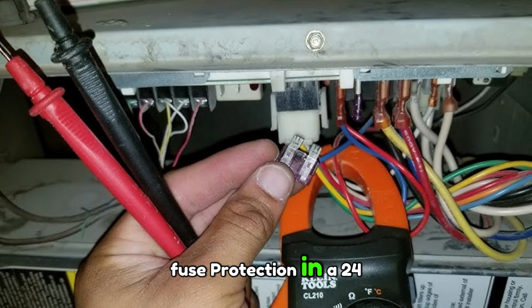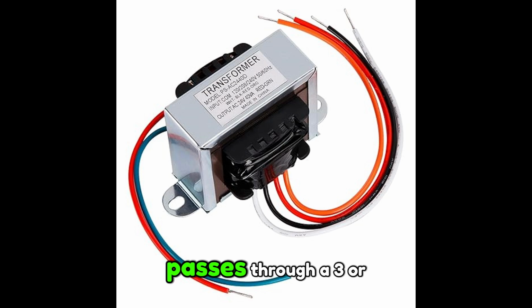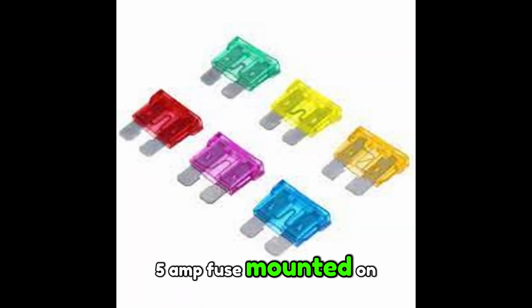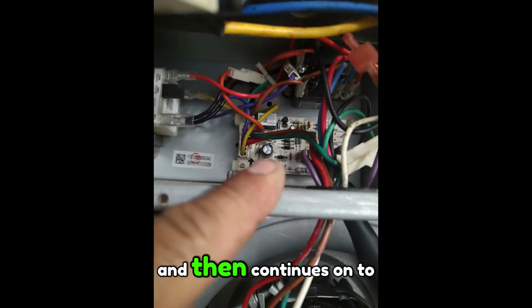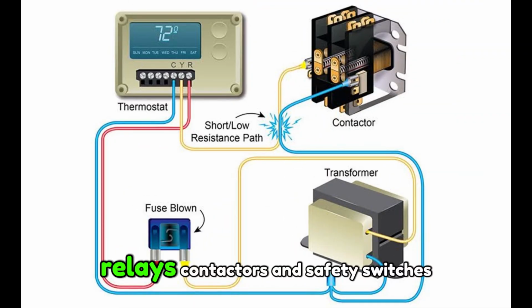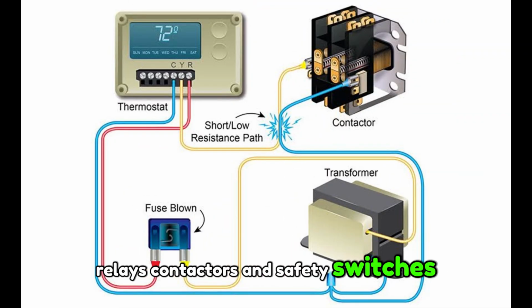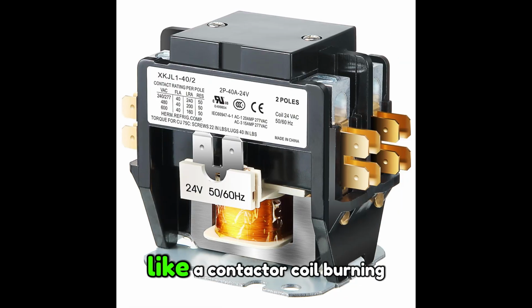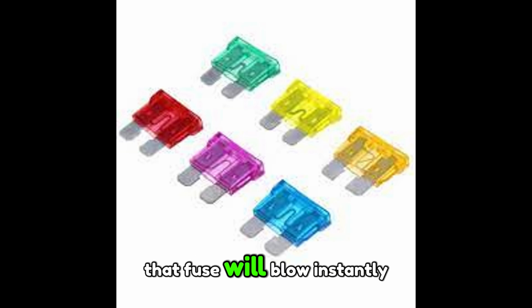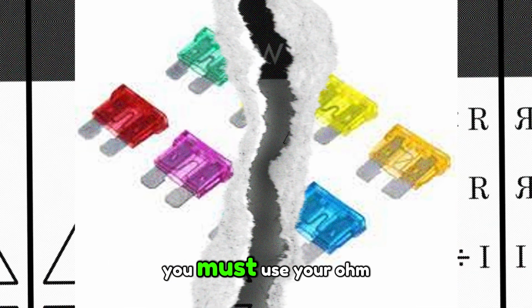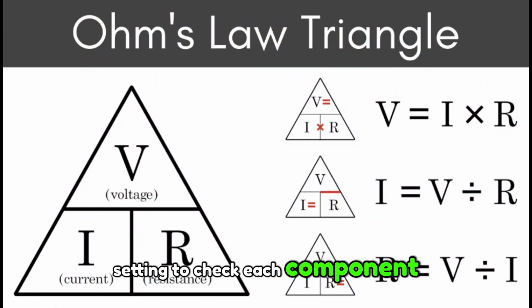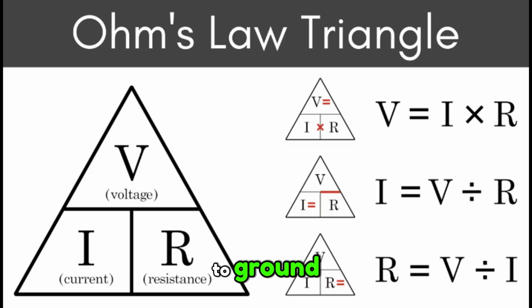Fuse protection. In a 24-volt circuit, the wire comes out of the transformer, passes through a 3 or 5 amp fuse mounted on the control board, and then continues on to thermostats, relays, contactors, and safety switches. If there's a short, like a contactor coil burning out or a wire touching metal, that fuse will blow instantly. You must use your ohm setting to check each component. If a wire has shorted to ground, you'll see 0 ohms or a very low number.